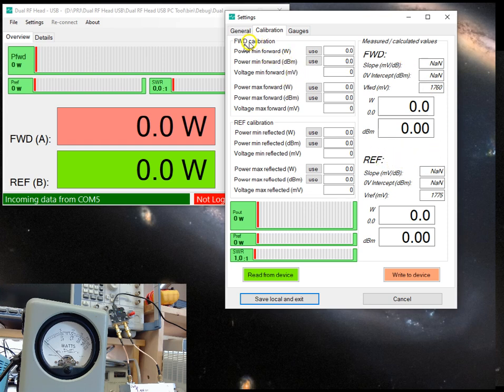On the left side, the top group here is the forward or the A port, and the one below is the ref calibration, that is the B port. And you need to tell the program or the device a calibration point for the minimum power and for a maximum power. Let's say that you have a power amplifier you're going to measure that will give out 500 watts. It does not make sense to calibrate it at 1 watt and 2 watts because you don't have enough spread from low to high power. So use the lowest power you can adjust and use the highest power or close to the highest power you can. You will get the best response from the device. I will show you in a moment how that works.